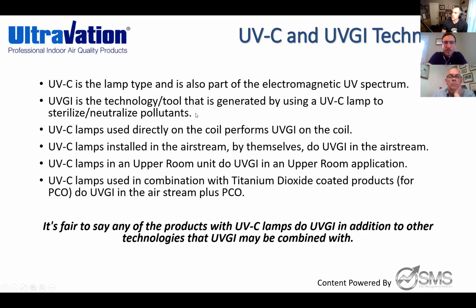UVC lamps used directly on the coil perform UVGI on the coil. UVC lamps installed in the airstream by themselves do UVGI in the airstream. UVC lamps in an upper room unit do UVGI in an upper room application. UVC lamps used in combination with titanium dioxide coated products for PCO do UVGI in the airstream plus PCO.